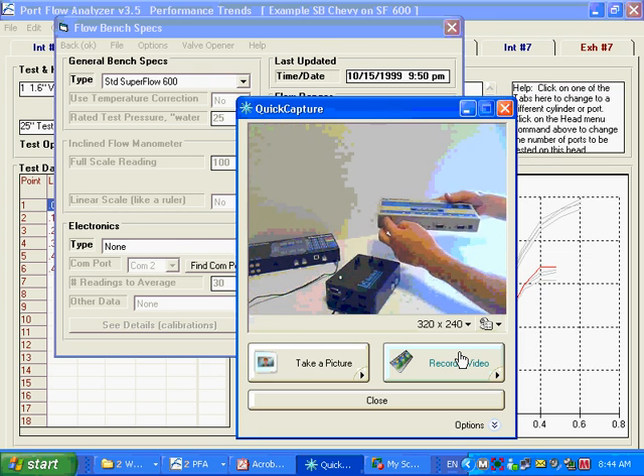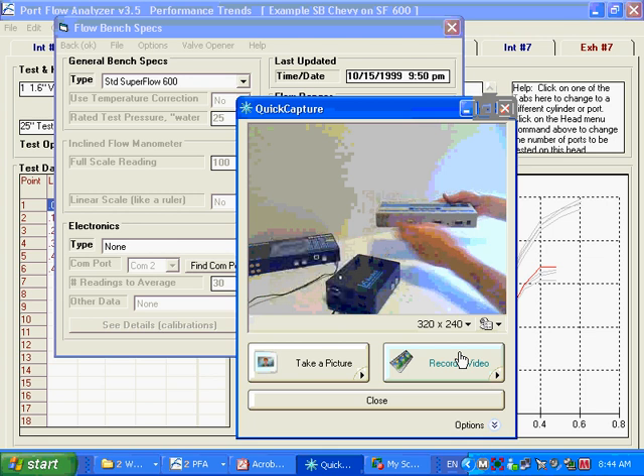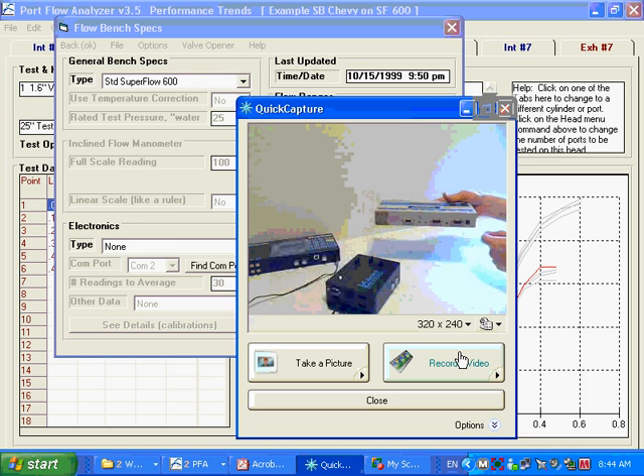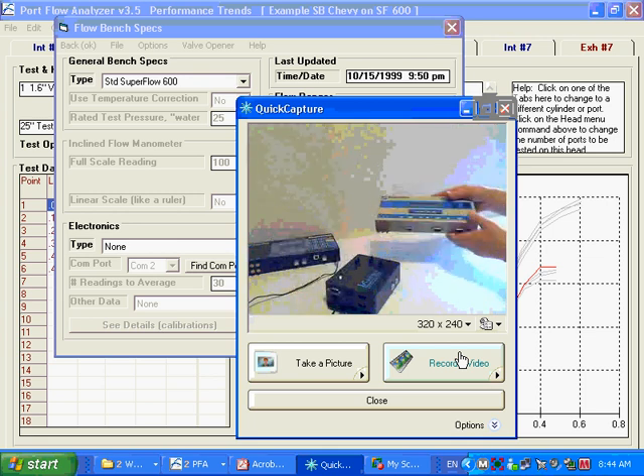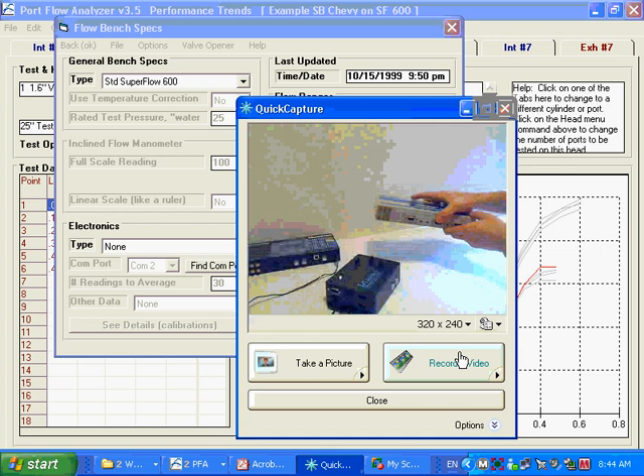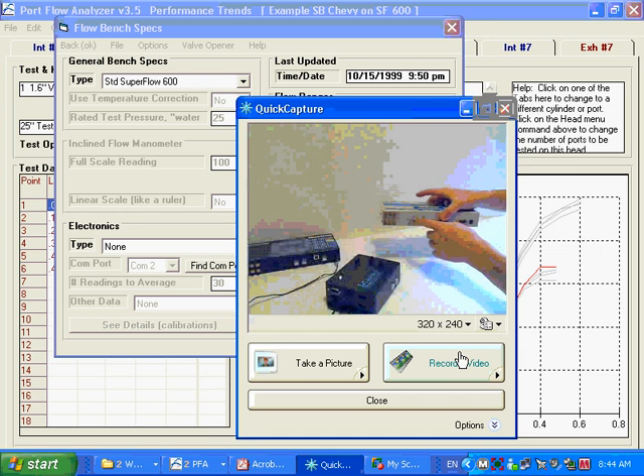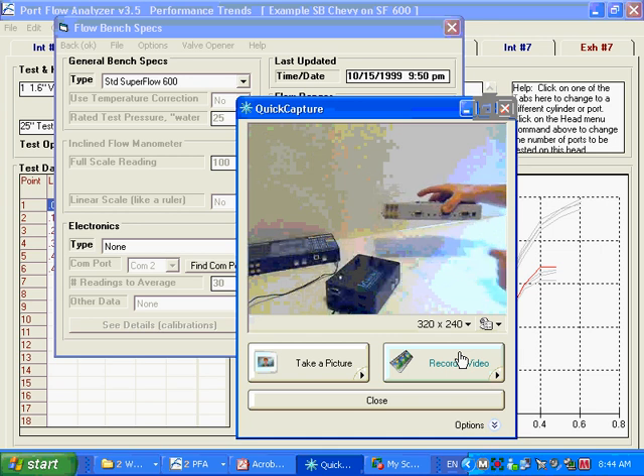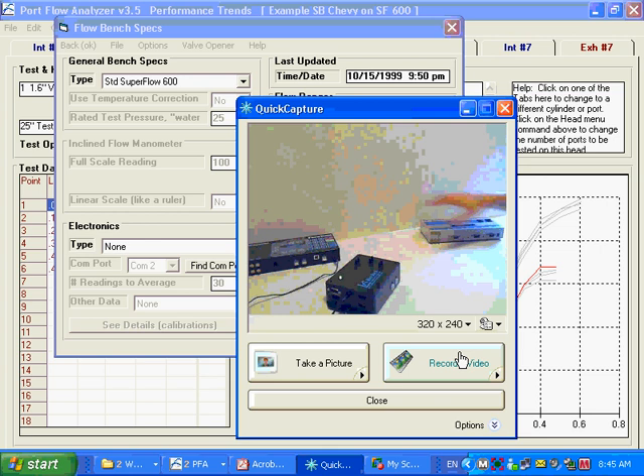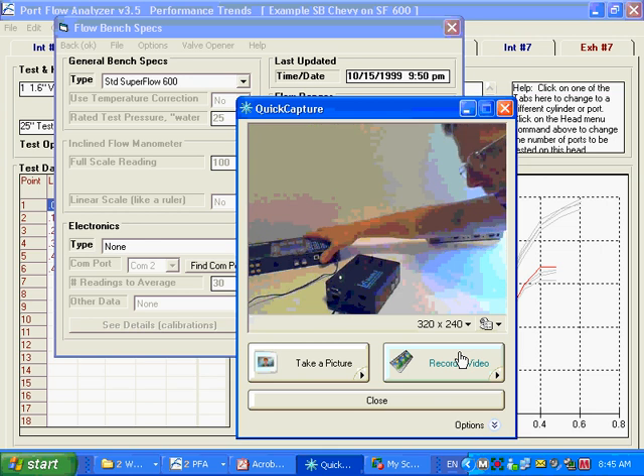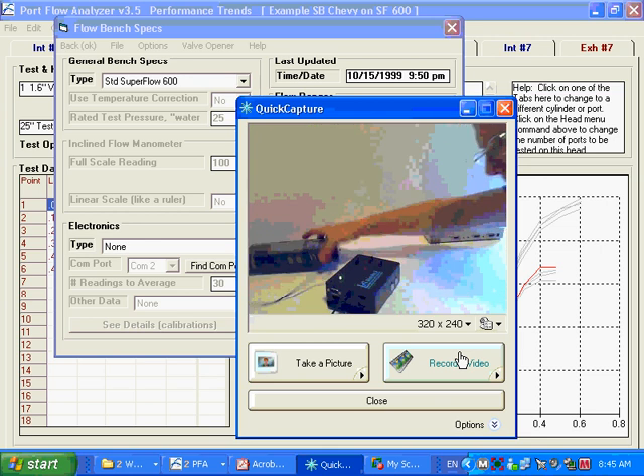your incline manometer, your flow pressure, and the pitot tube if you wanted it, a couple temperature inputs, and a swirl meter input, I believe it's J3 here, and your communications cable to your computer.